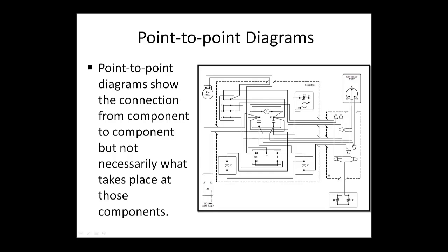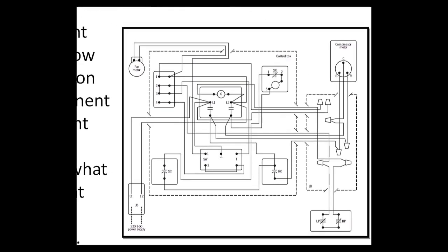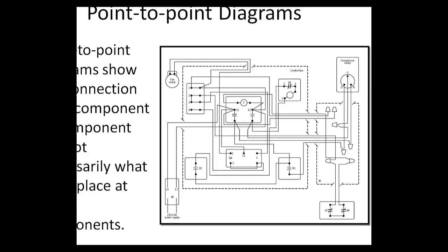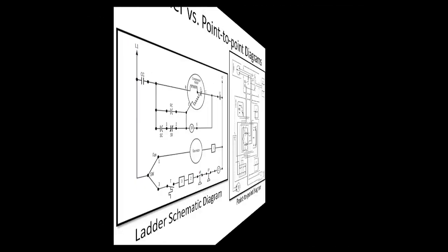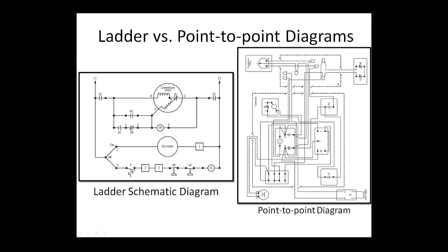Point-to-point diagrams show the actual physical wiring connections as they are made at the factory. Because it is difficult to trace individual circuits, these diagrams are not intended to be used for determining sequences of operation or for troubleshooting. For example, consider the point-to-point drawing for a heat pump circuit shown on this slide — it would be extremely difficult to follow the sequence of operation. Notice how much easier it is to determine the sequence of operation when reading the ladder schematic. You can see why ladder schematics are better suited for use as troubleshooting tools, rather than point-to-point diagrams.